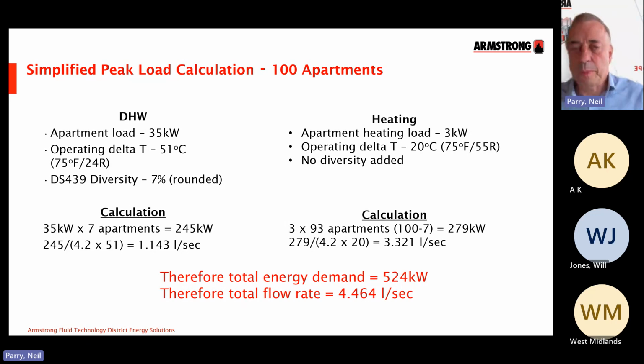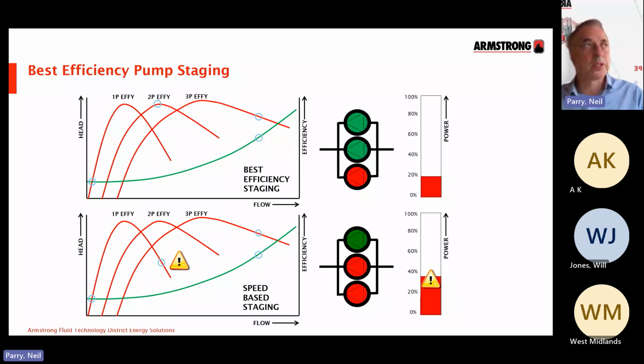So I want to talk very briefly about pump staging, best efficiency pump staging, as we call it. This is an Armstrong technology. What I've hopefully explained is the benefits of maximizing that delta between peak flow and, if you like, low flow conditions. That range of flow rates is best provided from multiple pumps rather than one single big pump, because one single big pump is going to struggle to back itself down to the low enough flow rate that's required for the low demand times. And if that pump's been oversized as well, it's going to be doubly difficult for it to do.